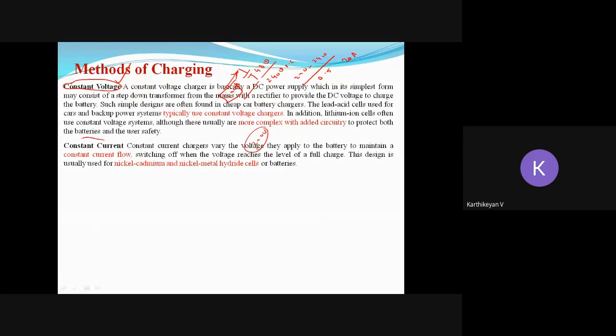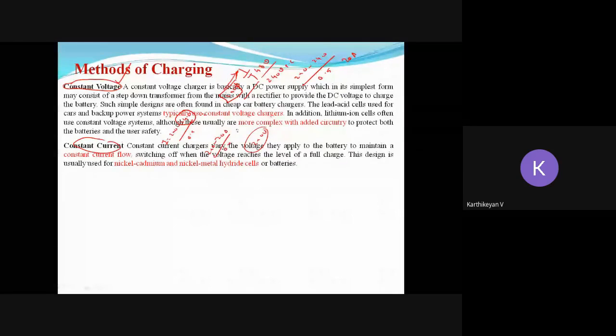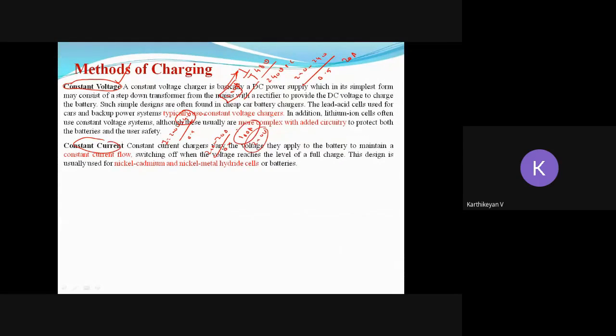So why constant current from the research point of view? As I told you, I equals to the same thing. For example, 250 minus 240 upon, say, 0.5 as the R value. When SOC rises as the electric vehicle keeps charging, what happens when the battery becomes empty? Empty means the battery stack voltage will be like 200 only. So 250 minus 200 when it is 0.5, you get 100 ampere. That means at the time of starting, when the battery is empty, your current will consume 100 ampere from the converter. So 100 ampere it has to load.